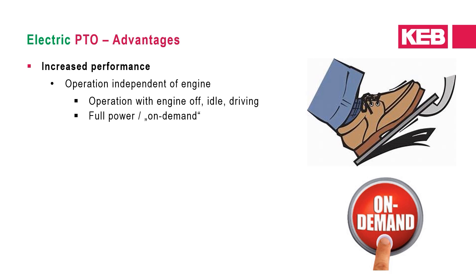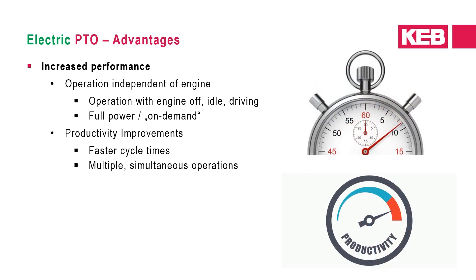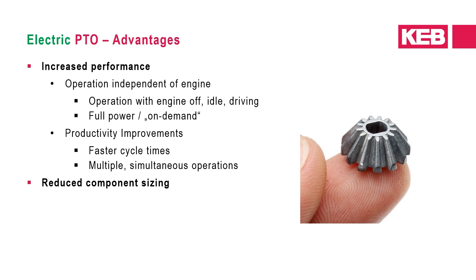On the other hand, there are several advantages to electric PTO. The first benefit is increased performance. With the operation of the auxiliary decoupled and independent of the engine, work can be performed under any condition — whether the engine is off, idling, or while the vehicle is being driven — allowing for full power from the auxiliary on demand. This can increase productivity by reducing cycle rates and allowing multiple operations to run simultaneously. The second benefit is reduced component sizing: an auxiliary decoupled from the engine can be right-sized according to the auxiliary's optimal operating point and actual load requirements, eliminating oversizing from worst-case scenarios such as heavy auxiliary load during engine idle.